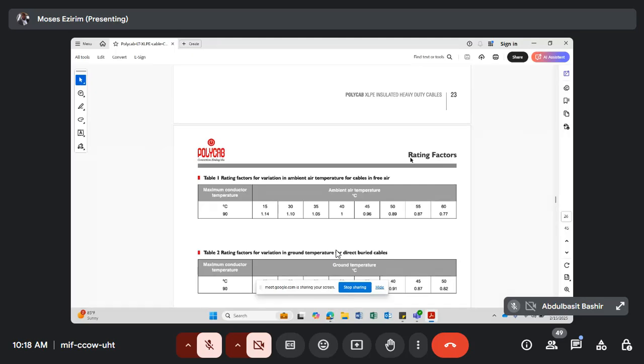Can you see the rating factors? Can you see rating factors for variation? That means if I'm suspending my cable and not passing it under the ground - there are two ways in which you can route your cable: either fly it in the air, or bury it in the ground. So if I'm flying my cable in the air, I need to consider ambient air temperature. Can you see it? Ambient air temperature - you can see the degrees.